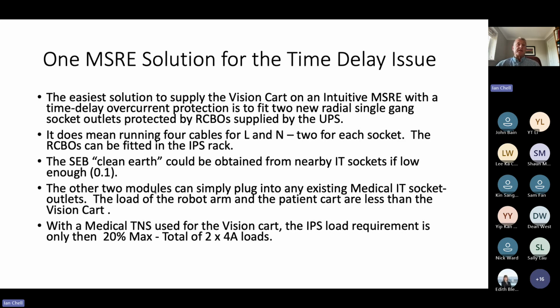And if you're retrofitting, you can easily find a clean earth from a nearby supplementary equipotential bonding connection point from nearby IT sockets, but you've got to make sure it's low enough because it's a time delay trip. And the other two modules, because the MSRE comes with 3 parts, can simply plug into any existing medical IT socket outlets. So that means the load of the robot arm and the patient cart are much less than the vision cart. Okay, so that doesn't really affect the medical IT too much, but obviously you've got to look at the UPS. So when you use medical TNS for the vision cart, the IPS load requirement comes down to 20% max, which is 2 times 4 amp loads. Okay.